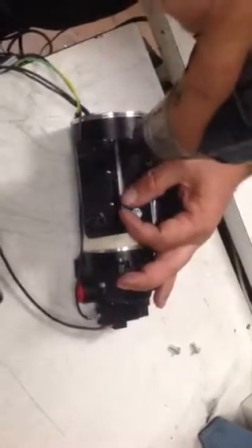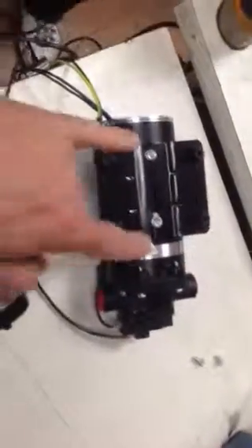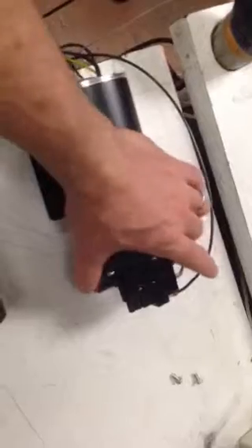In this case, we have a very, very low torque driver here. We're going to give it a low torque, but you can just hand tighten the bolts there. Now you're complete. You've attached your new motor onto your pump head. At that point, the pump is ready to be plumbed into your system and tested accordingly with your spray wand. As usual, if there's any switch setting adjustment to be made, here's the set screw, and as normal you would adjust the pump according to your machine for minimizing of any kind of cycling. That completes the disassembly of the pump head and reassembly onto the new motor.